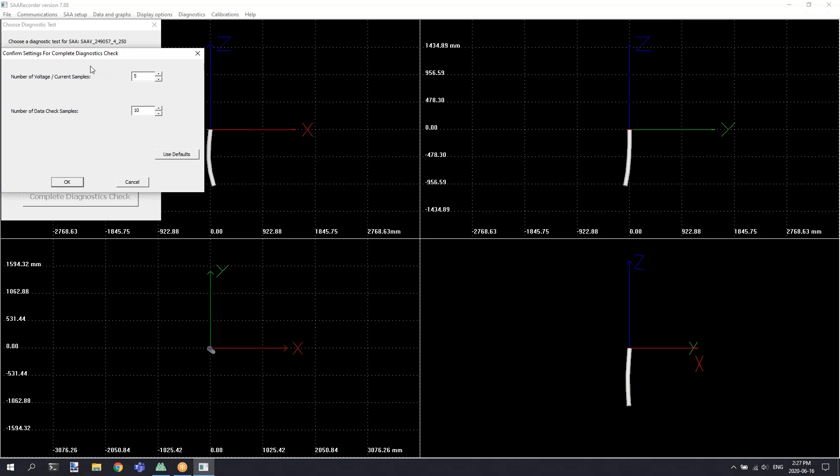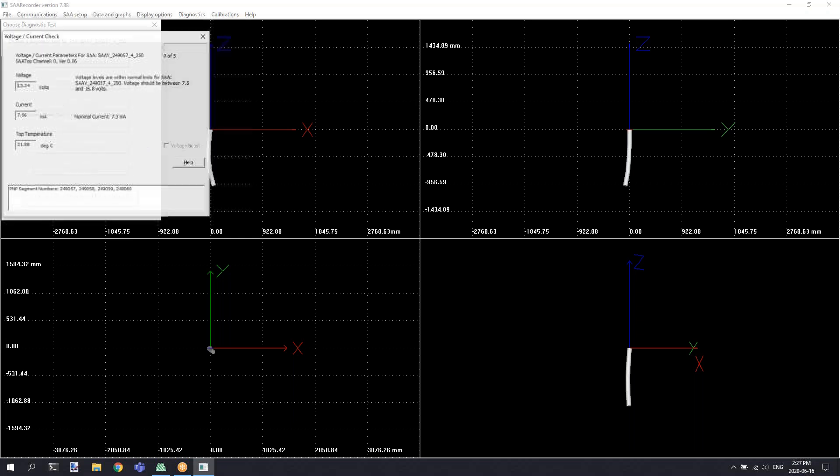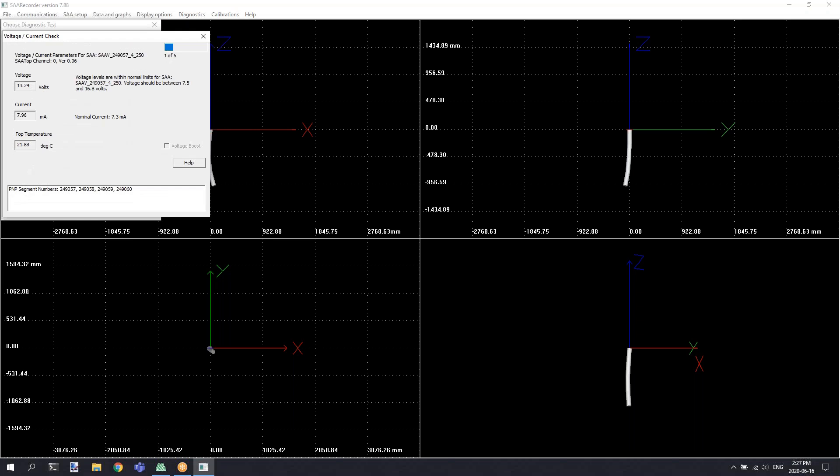By default, the number of voltage and current samples and the number of data check samples are 5 and 10, respectively. And we recommend leaving those values high, as repeated numbers of tests will often be good when trying to troubleshoot any intermittent problems. Clicking the OK button will start the tests, and you'll see various windows pop up with progress bars as the diagnostics tests are performed on your instrument.